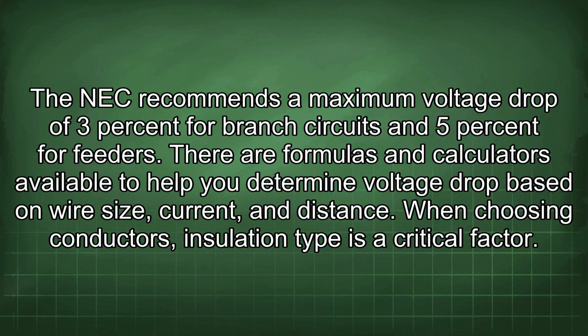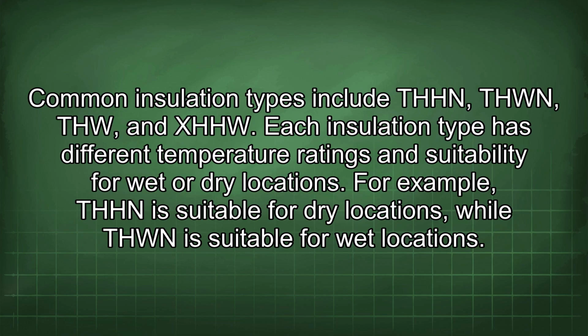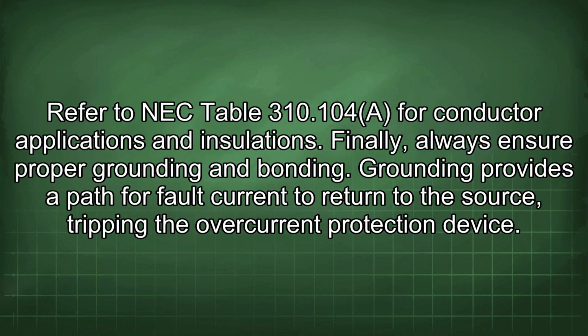When choosing conductors, insulation type is a critical factor. Common insulation types include THHN, THWN, THW, and XHHW. Each insulation type has different temperature ratings and suitability for wet or dry locations. For example, THHN is suitable for dry locations, while THWN is suitable for wet locations. Refer to NEC Table 310.104 for conductor applications and insulations.